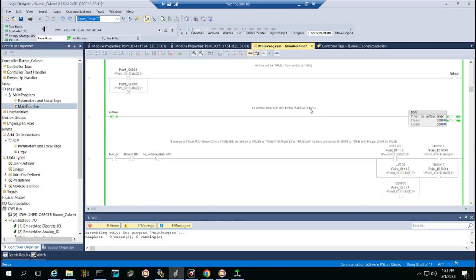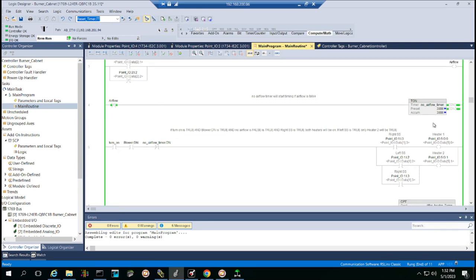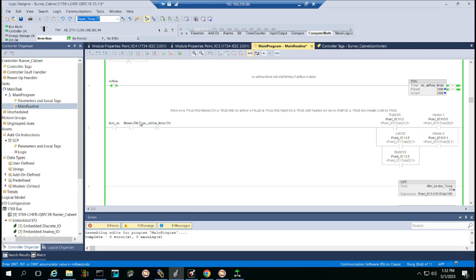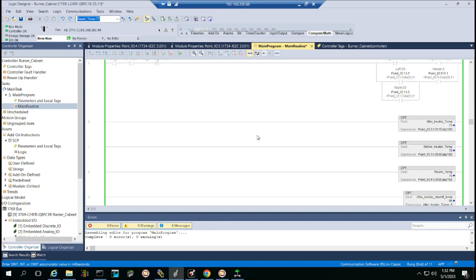And so this thing's kind of inconsistent. It's got that little fan on it, and when the blower blows, the fan kind of kicks up, and it's not always accurate. Sometimes it flickers back and forth. So if it's not true for more than 3 seconds, we have this no airflow timer, and that'll shut off the power to our heaters. And here we have, if the selector switch is turned to the right, both heaters will run. If it's turned to the left, just one heater will go.